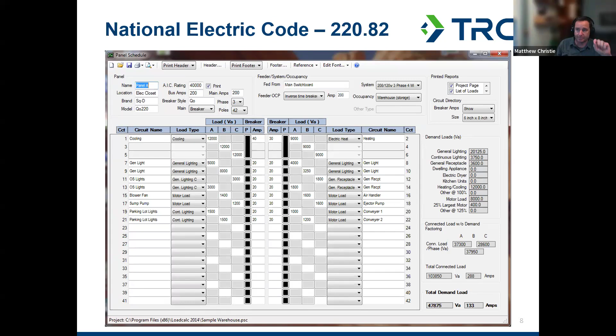On a 200 amp service it's 80%, so 160 amps is the threshold. That gives you a little wiggle room if you cross over briefly and come back down. So 80 amps is the safety factor for a 100 amp home, 160 amps for a 200 amp home, and you can do the math for other sizes.